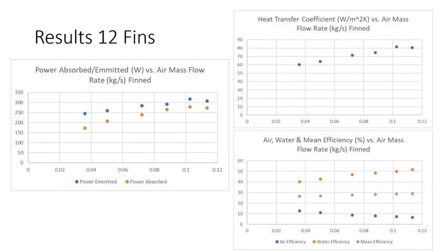One possible reason for this is the presence of the thermal conductivity paste. It was used to increase the surface contact between added fins and the tubes. It formed irregular shapes, however, which may have disrupted the airflow through the heat exchanger. Another possible source of error is the aforementioned surface contact. Although the thermal conductivity paste was used to improve that, the contact was not as seamless as that of the manufacturer-provided fins.